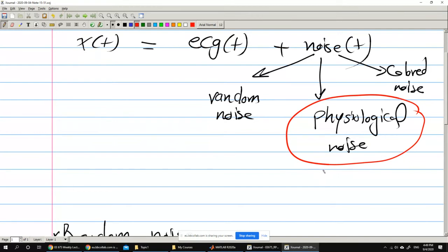And they are very tricky, because imagine that the doctor complains about the ECG having an artifact, and you test the same system on a different patient, and you don't see anything. The doctor says, I saw an artifact, but I don't see it now. Okay, so it's very tricky because it depends on the patient.